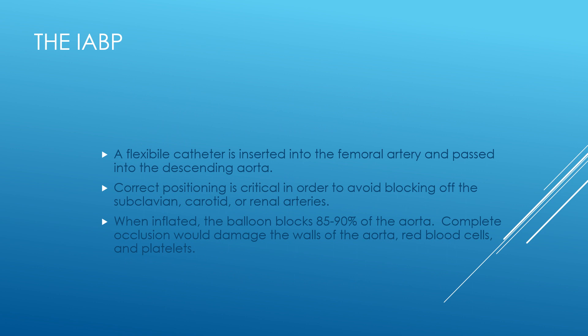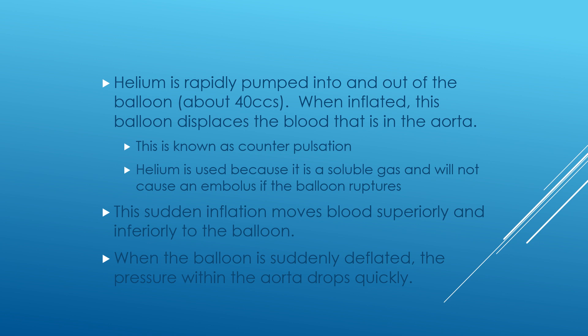The intra-aortic balloon pump is a flexible catheter inserted into the femoral artery and passed into the descending aorta. Correct positioning is critical in order to avoid blocking the subclavian, carotid, and renal arteries. When inflated, the balloon blocks 85 to 90 percent of the aorta. Complete occlusion would damage the walls of the aorta, cause hemolysis, and damage platelets causing platelet dysfunction. Helium is rapidly pumped into and out of the balloon, about 40 ccs. Helium is used because it is a soluble gas and will not cause an embolus if the balloon ruptures.